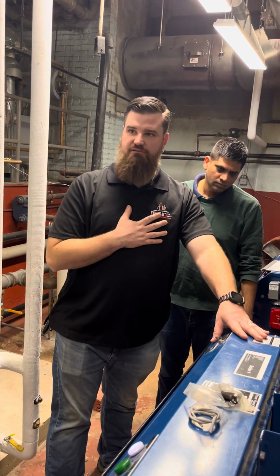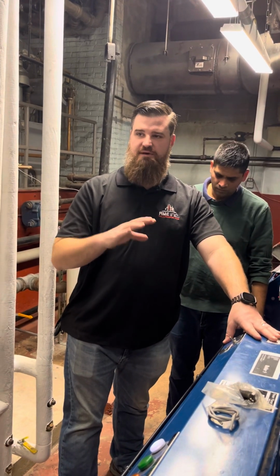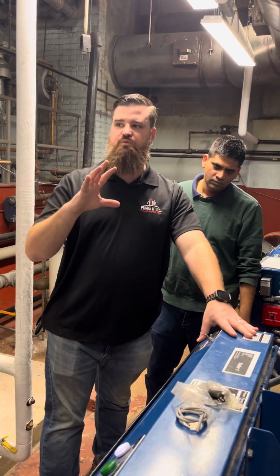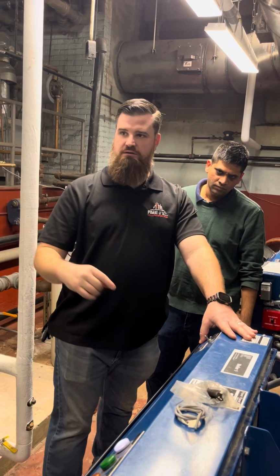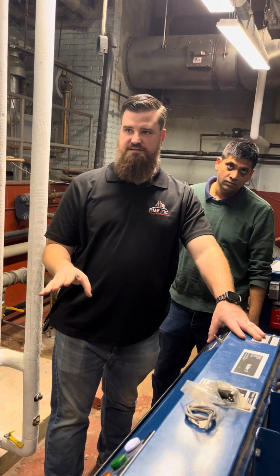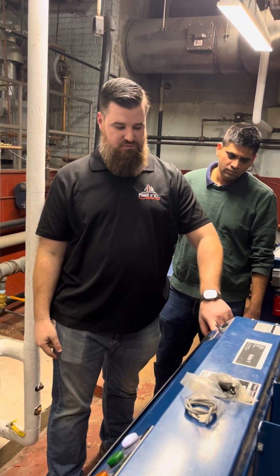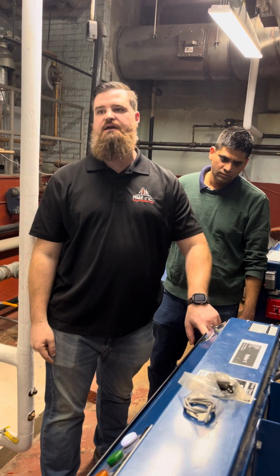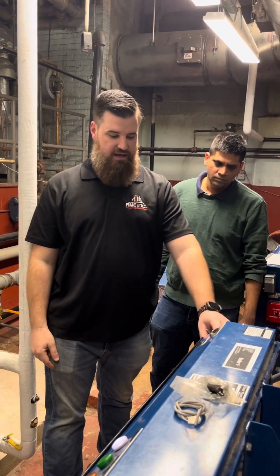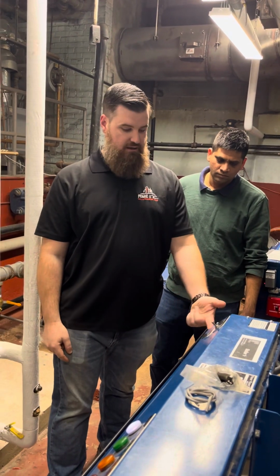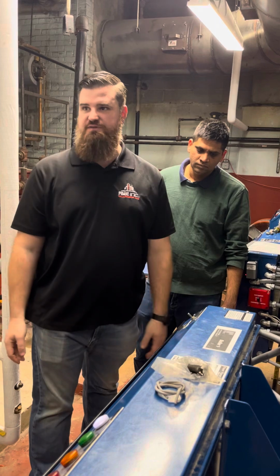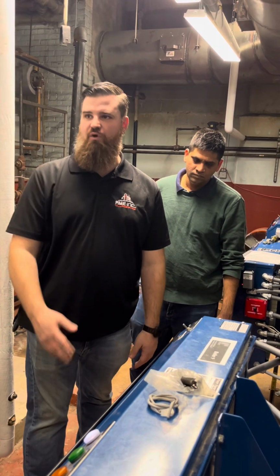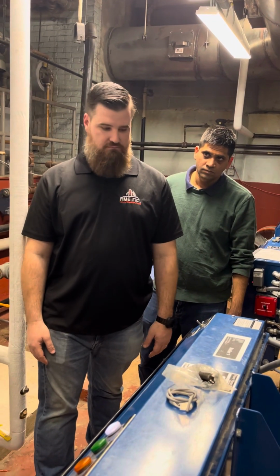I have no control of this boiler. The only control the BMS has of any of these boilers is whether or not we're telling the boiler to run or we're telling it to be off. That is it. That's it. Okay? When you look at this relay, if this light is on, we're telling it to run. But again, if I come over here and I put that switch in open, it doesn't matter. You bypass what this relay is designed to do, and now the boiler's not going to run. If somebody hits that by mistake or something like that.